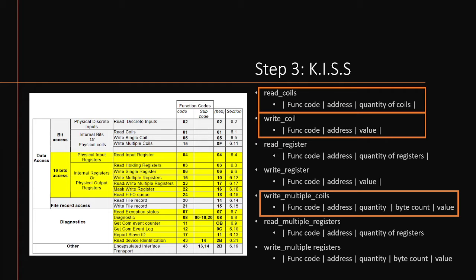The reason for this is because a lot of times when someone's using this type of system that speaks Modbus, you're probably going to be reading the status of a coil. A coil, which I should explain here, is usually a discrete value of 0 or 1. A register can be any 2-byte integer. This is important because it also explains why these are commonly used. Coils, since it's a discrete value, can represent on or off, whereas a register is probably going to be more of a value like the phase angle of a generator, or maybe the voltage level of some device it's connected to. So it's less discrete as 0 or 1, but more like I can set a floating point value there and set what it's going to tell another device to be.